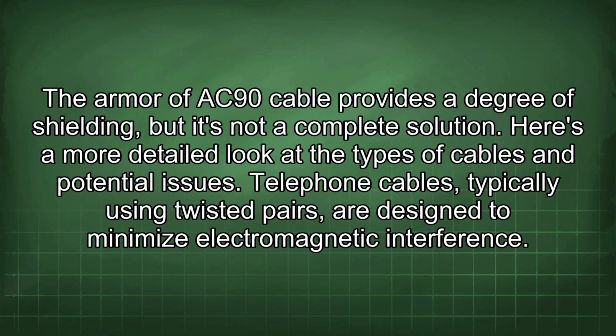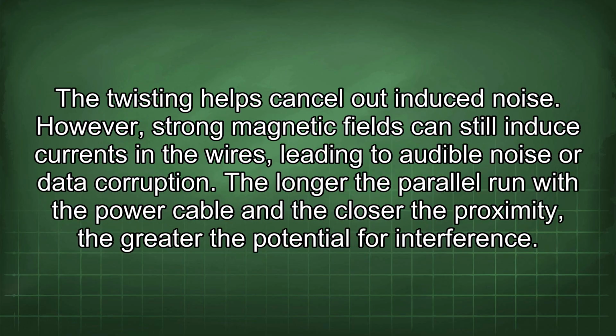Telephone cables, typically using twisted pairs, are designed to minimize electromagnetic interference. The twisting helps cancel out induced noise. However, strong magnetic fields can still induce currents in the wires, leading to audible noise or data corruption. The longer the parallel run with the power cable and the closer the proximity, the greater the potential for interference.